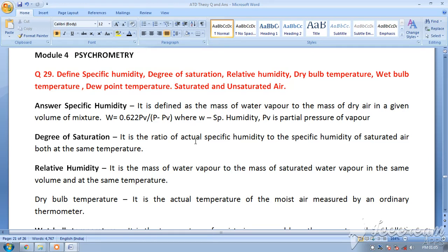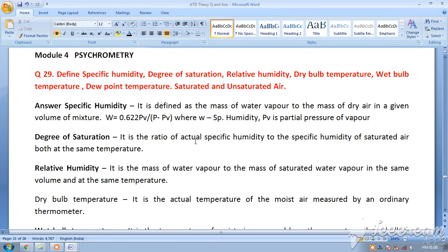The lower the temperature of air, the lower the amount of water it can hold, and the higher the temperature, the higher the amount of water it can hold — ranging from 0 grams to almost 40 grams depending on temperature. In psychrometry we normally study up to about 40–45 degrees centigrade since that is the typical ambient temperature range. So degree of saturation is the ratio of actual specific humidity to the specific humidity of saturated air at the same temperature, because temperature changes the capacity of air to hold water.